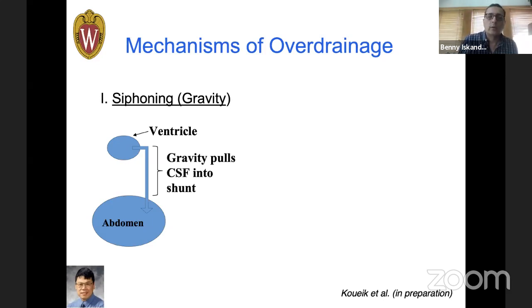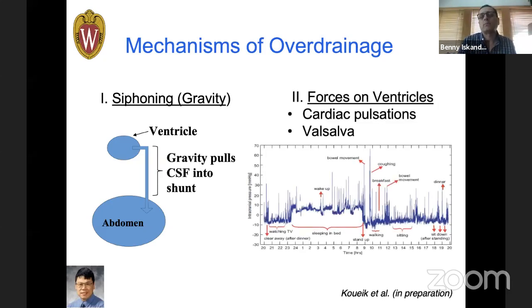So as we all know, gravity is a major cause of why shunts drain. And we feel that gravity causes overdrainage. However, when we simulated our shunt systems and did some benchtop testing, we found that gravity is not the only mechanism to overdrain shunts. There's another mechanism that can happen even when you're in the supine position, and that is pulsations. Imagine that you're lying in bed and all of a sudden you start to cough. Every cough is putting a lot of pressure in your brain, 50, 60 millimeters of mercury, which far exceeds any shunt valve mechanism that is available on the market, which means that every time you cough, you're going to drain way beyond your average ICP.